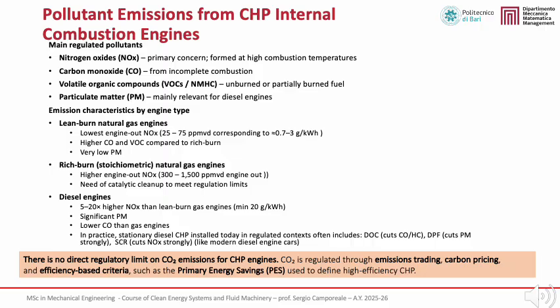We now consider the main pollutant emissions associated with CHP systems based on internal combustion engines. The principal regulated pollutants are nitrogen oxides, or NOx, which represent the primary environmental concern because they are mainly formed at high combustion temperatures. Other relevant pollutants include carbon monoxide, produced by incomplete combustion, volatile organic compounds, or VOCs, originating from unburned or partially burned fuel, and particulate matter, which is mainly relevant for diesel engines.